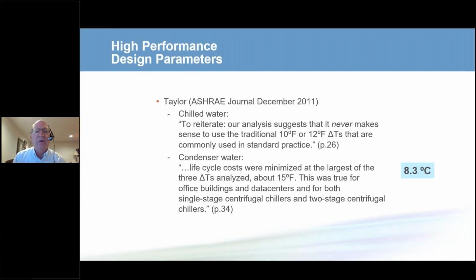This is the summary of Mr. Taylor's article from the December 2011 version of the ASHRAE Journal. There are a couple of important points here. Not only is he saying the delta T should be larger, but he said a couple of other things in the summary. And that is, this is true for office buildings and data centers. Now, why would he say that? If we think about the cooling load profiles of data centers, they're constant. Once a data center is up and built, it has a constant load every hour of the year. Whereas office buildings change depending on the time of day. The load profile varies by season, particularly in a climate like ours. Not so much perhaps in India, but what Mr. Taylor was saying is that reducing the flow rates is good whether your loads are constant or they vary. So no matter the application, it makes sense.